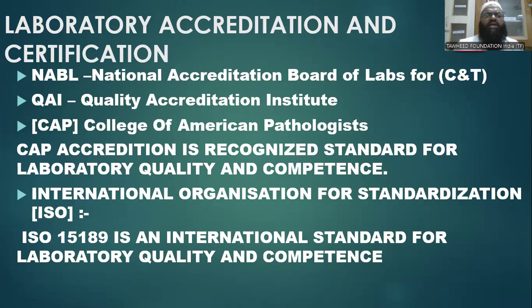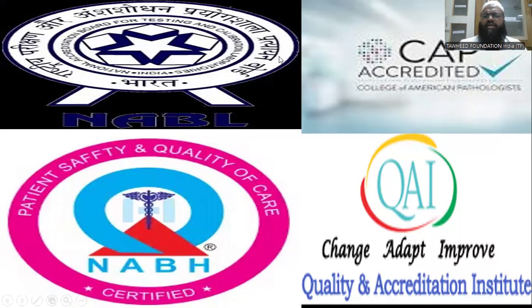And here we see the standard of the International Organization for Standardization, ISO. For laboratories, we use ISO 15189 as an international standard for laboratory quality and competence. Under ISO 15189, there is an updated version, 15189:2022. Before it was 2012, now it is 2022.